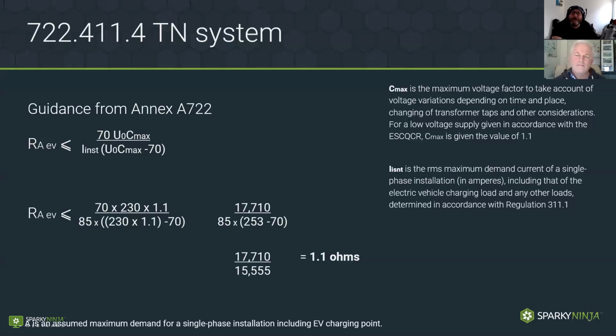And the goal here, obviously, is that the voltage won't go over 70. That's the point. That's why 70 is stuck in that formula. Okay, so the conclusion with this second option of putting in an electrode near the actual charge point. Remember, that's not converting to a TT system. This is connecting onto the PME. This is not a conversion to TT.